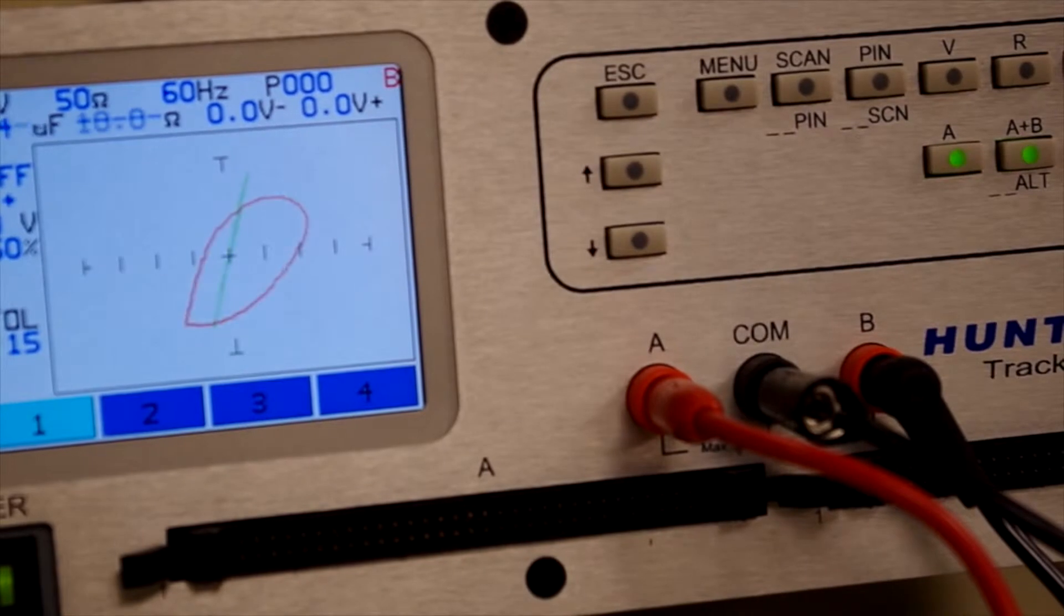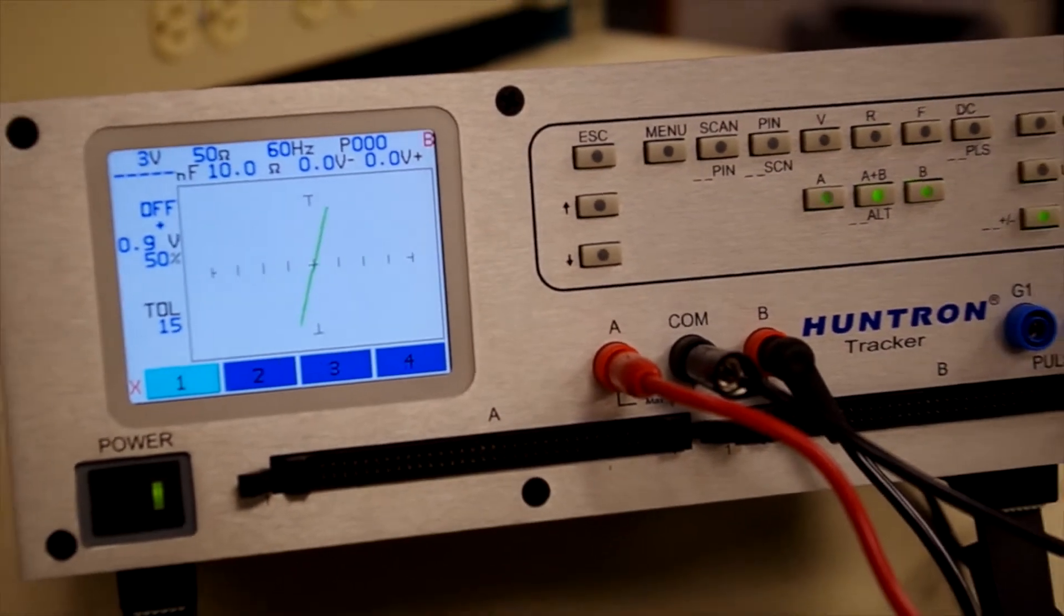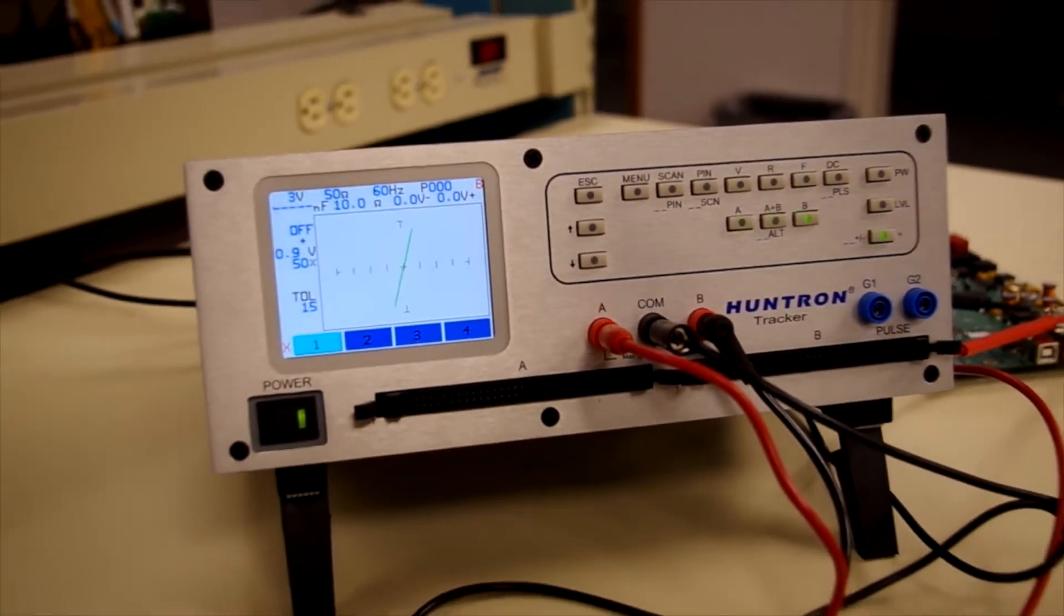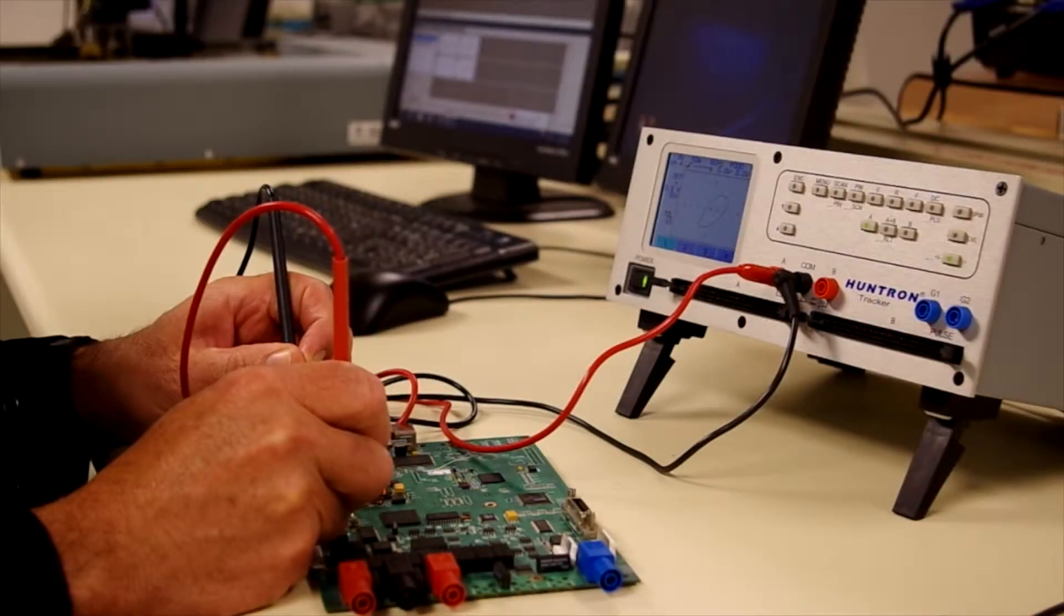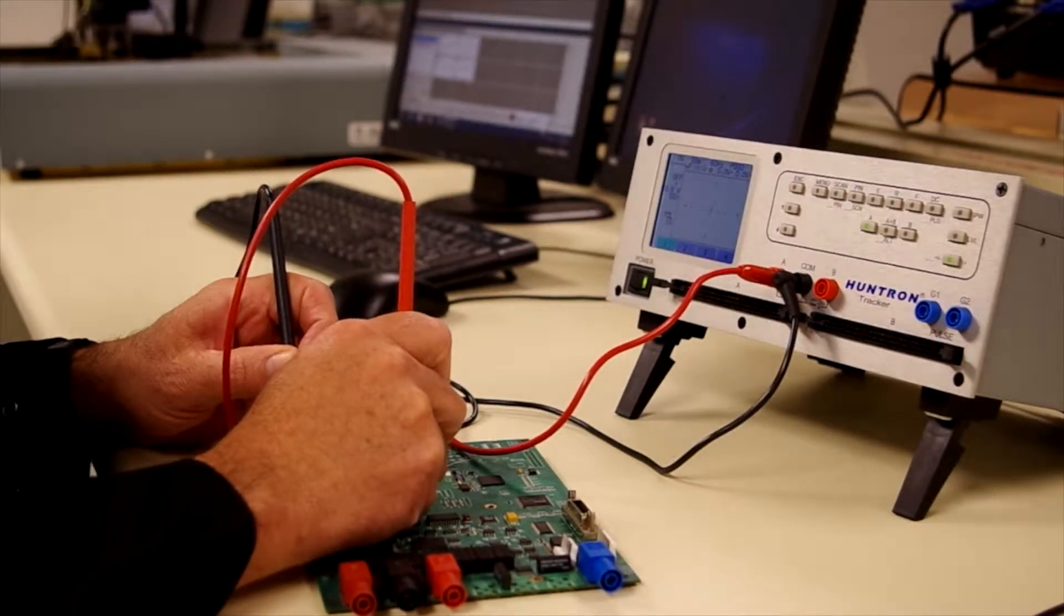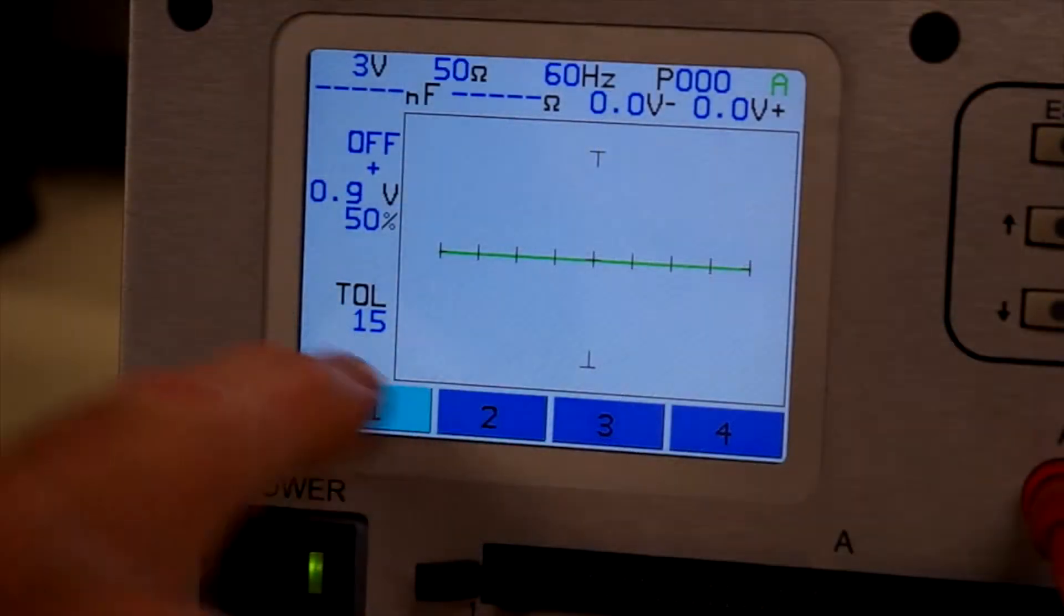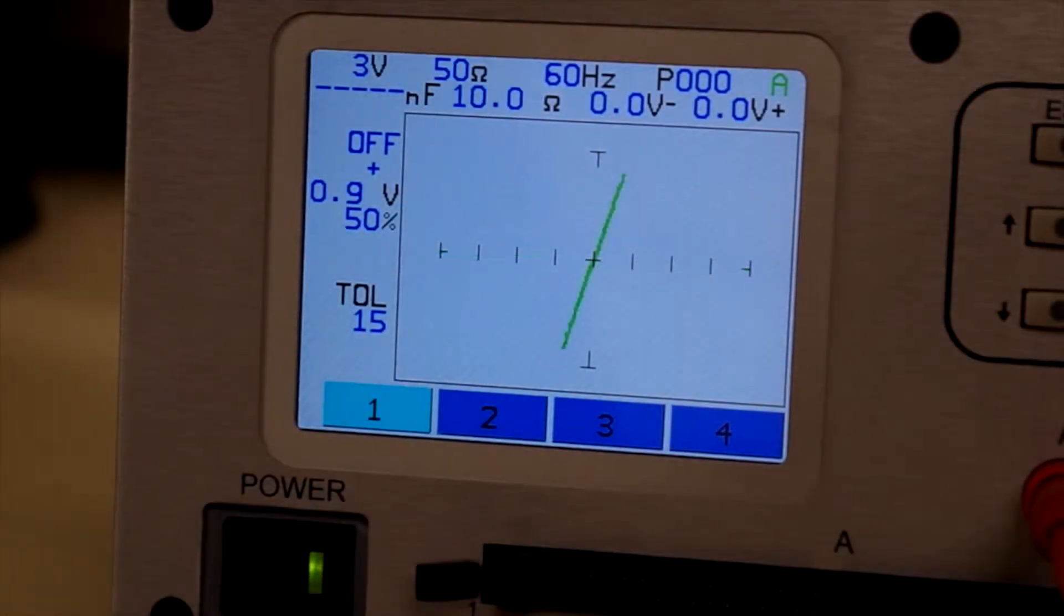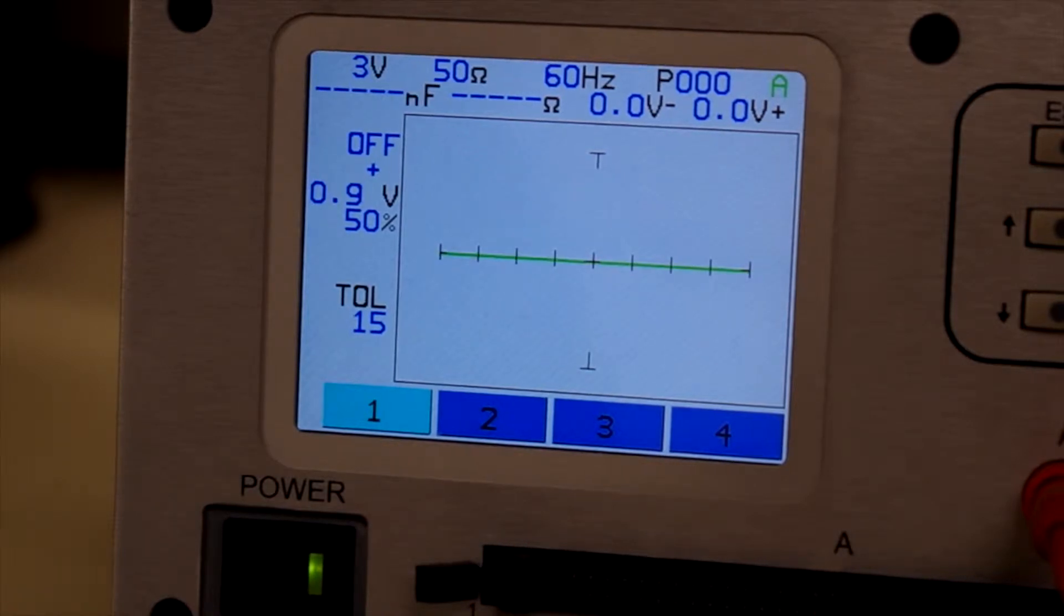The Tracker 3200S is a power-off troubleshooting tool that uses analog signature analysis to help diagnose and locate problems on printed circuit boards. Similar to a curve tracer, analog signature analysis uses a voltage versus current signature that models the electrical nature of the circuit being tested.